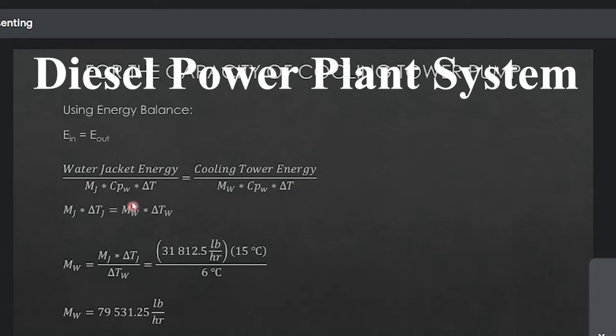Substitute lang natin yung values, i-manipulate natin, isolate natin itong mass ng water para sa cooling tower. Ito yung lalabas na formula natin: multiply lang natin 31,812.5 pounds per hour multiplied by 15 degrees Celsius divided by 6 degrees Celsius. Cancel yung Celsius natin, ang matitira is pound per hour. Ang mass natin ngayon for the cooling tower would be...